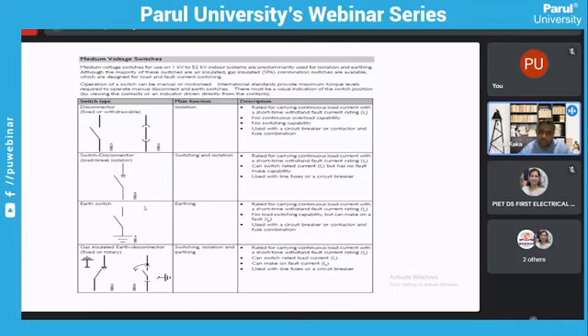Now coming to a gas insulated switchgear, it's normally done by the 3-position disconnector switch, which is connected with a breaker inside a gas tank. How exactly it works is that you open a breaker, it's all steady and static. You don't have any withdrawable parts or any sort of mechanism as what we are seeing in an insulated one.